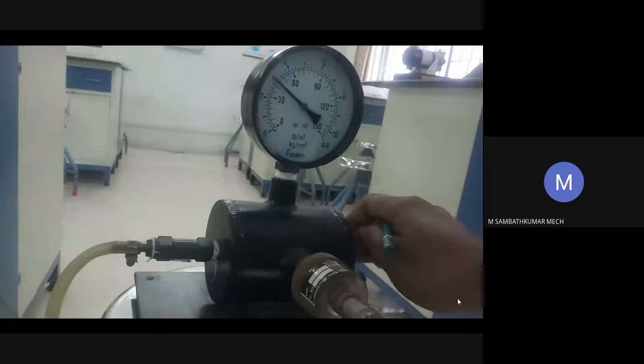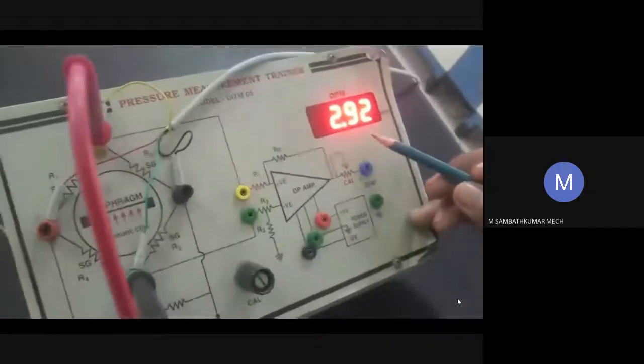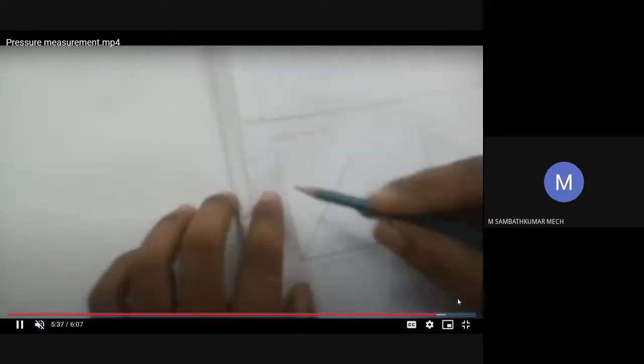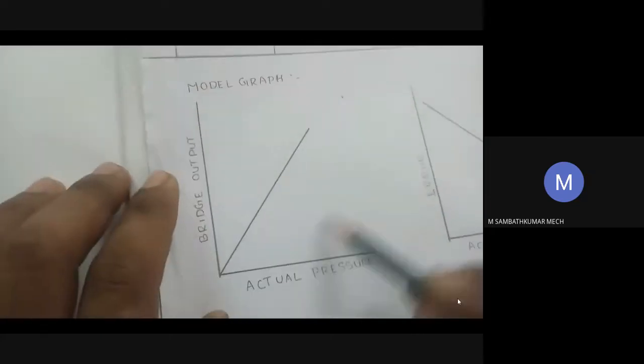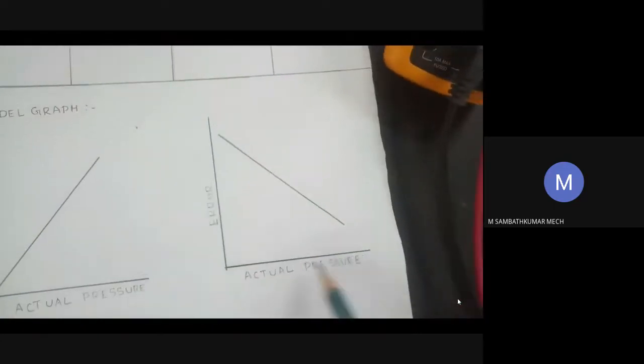And you should gradually reduce the pressure, up to 3, and again take the readings: the sensor reading, that is the indicated pressure, and the output bridge voltage. Continuously reduce up to 1 bar and take the readings. Model graphs are available, so based on the tabular column you should draw them. The model graphs are actual pressure versus bridge output voltage, and actual pressure versus percentage of error.